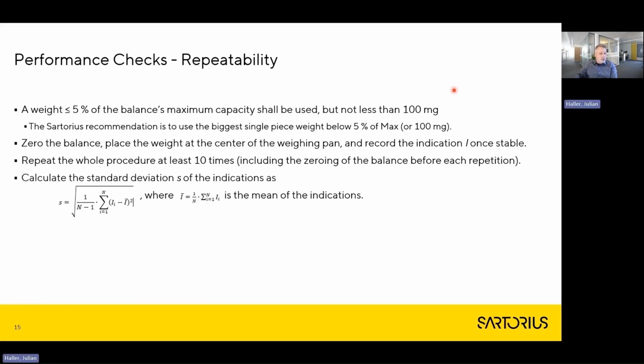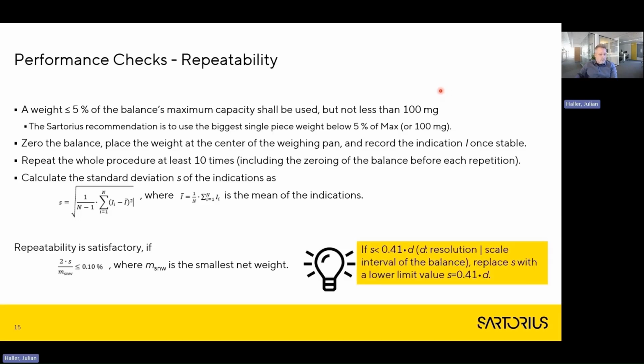Calculate the standard deviation S from the indications with the well-known formula for standard deviation. Repeatability is then satisfactory if 2 times the standard deviation divided by the smallest net weight is smaller than or equal to 0.10%. I will say something about the smallest net weight in a minute. Note that if the balance has a very good repeatability and the standard deviation is smaller than 0.41 times the resolution, this should be considered as a lower limit value, so replace the standard deviation with 0.41 times the resolution in this case.